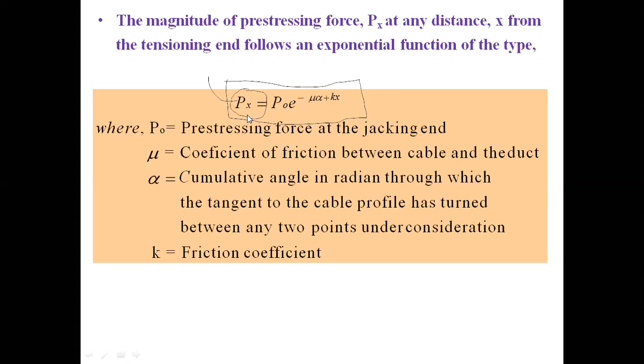Okay. So here, in the absence of the test data, why? Because this test data was not given exactly in the code. Why? Because these mu values and K values will be taken from an industry. So mu values always depend on the type of interface. Type of interface is nothing but how the strand or cable is connected or in contact with the duct. So here if the steel is moving on smooth concrete, your mu value is 0.55, which is given by the industry. If the steel is moving on steel fixed to the duct, which is touching the duct, then your mu value is 0.3.